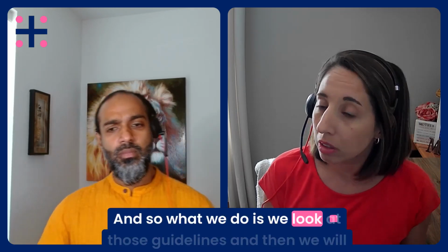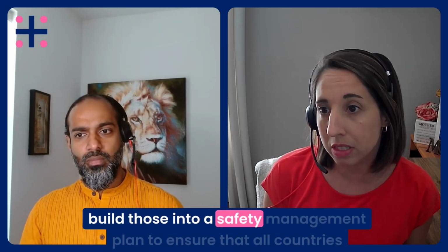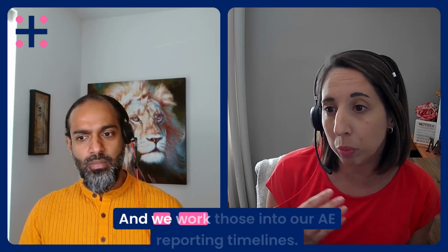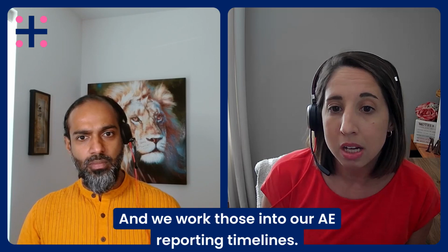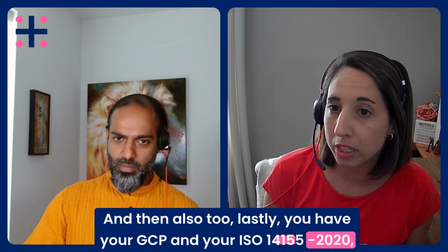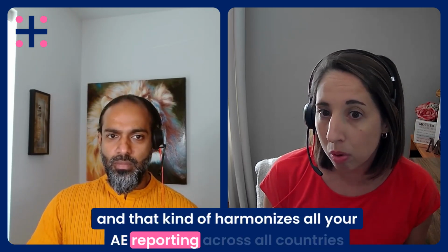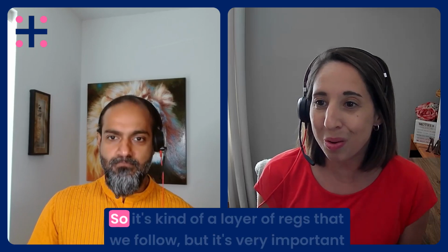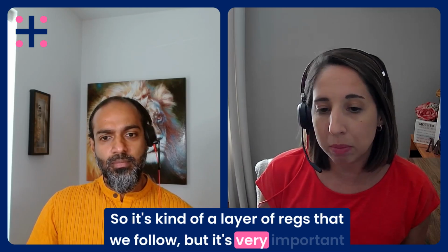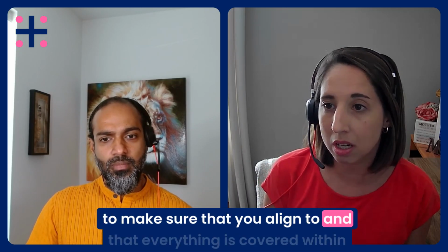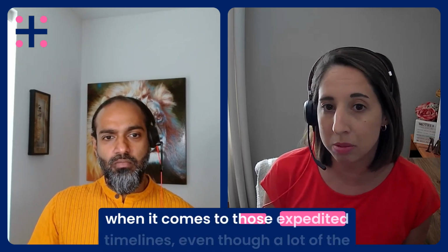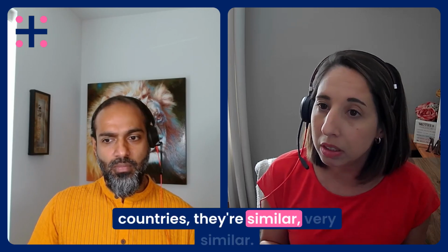And so what we do is we look at those guidelines and then we will build those into a safety management plan to ensure that all countries are followed, and we work those into our AE reporting timelines. And then also, lastly, you have your GCP and your ISO 14155/2020, and that kind of harmonizes all your AE reporting across all countries and regions. So it's kind of a layer of regs that we follow, but it's very important to make sure that you align to, and that everything is covered within your protocol and you're not missing anything when it comes to those expedited timelines.